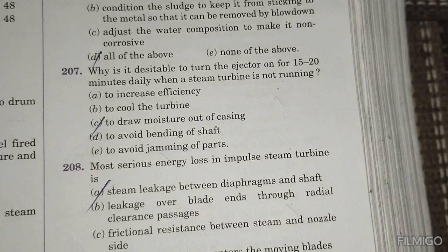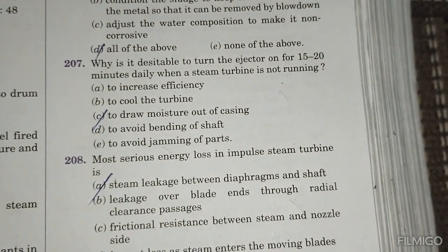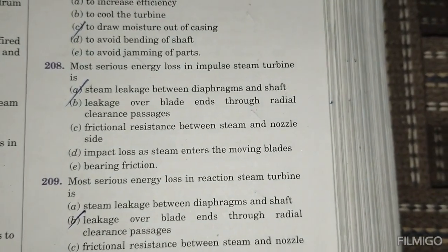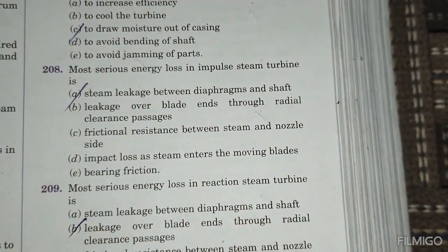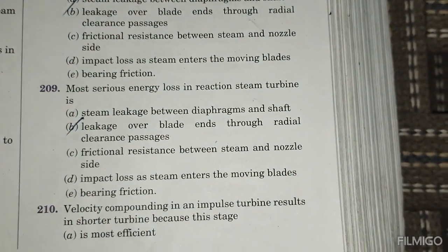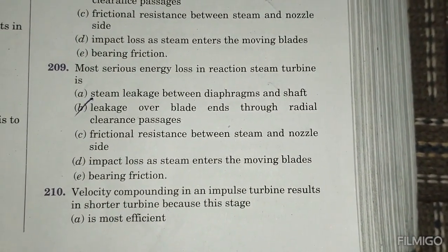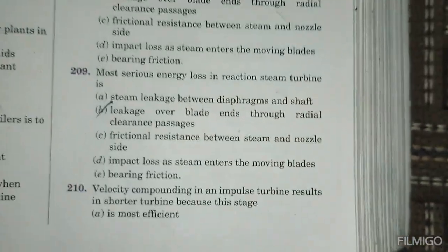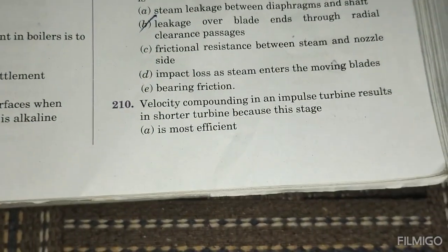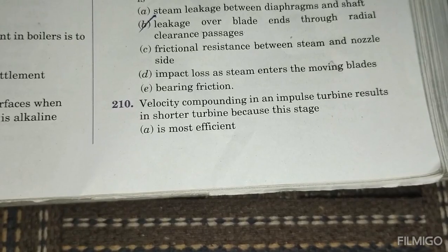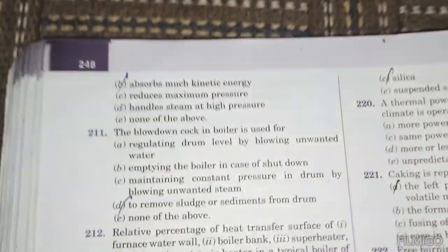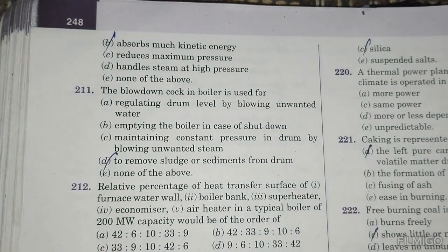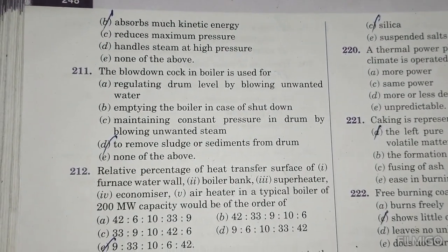The ejector is run for 15 to 20 minutes daily when the steam turbine is not running, to draw moisture out of the casing. The most serious energy loss in an impulse steam turbine is steam leakage between the diaphragm and shaft. The most serious energy loss in a reaction steam turbine is the leakage over blade ends through radial clearance. Velocity compounding in an impulse turbine is the result of a short turbine, with each stage absorbing much kinetic energy. The blowdown cock in a boiler is used to remove sludge or sediments from the drum.